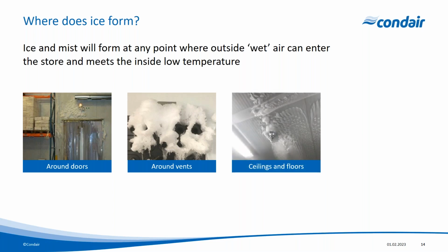Ceilings and floors. Again, here you can see a ceiling, and it's very common. It's just above the entrance to a cold store where air enters the cold store. It immediately rises up, it forms condensation, and that condensation goes on to freeze very quickly, and we get significant ice buildup inside the freezer store.